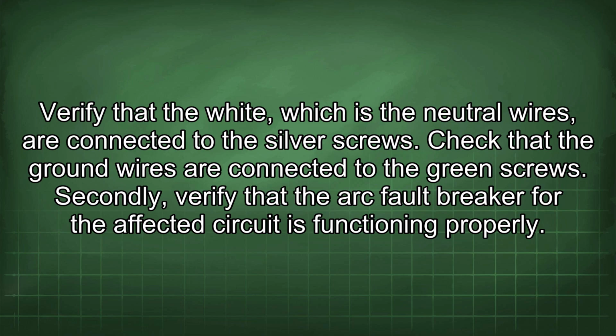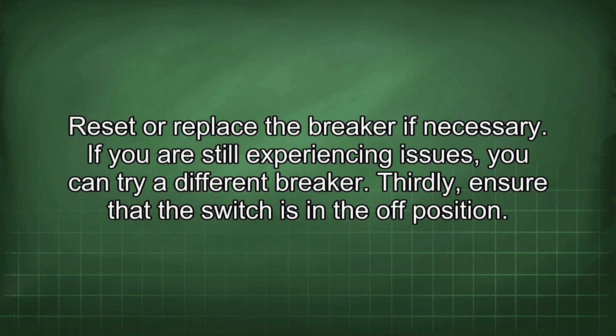Secondly, verify that the arc fault breaker for the affected circuit is functioning properly. Reset or replace the breaker if necessary. If you are still experiencing issues, you can try a different breaker.